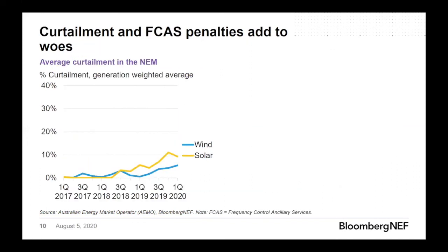Another problem on the grid is curtailment — generation that could have been generated but was not. In the first quarter of 2020, we found 6% curtailment of wind in the NEM. A lot of that was economic curtailment, but a lot was also system strength curtailment. This issue of system strength arises when there's not enough synchronous generation in that part of the grid — not enough coal, hydro, gas, or synchronous condensers.